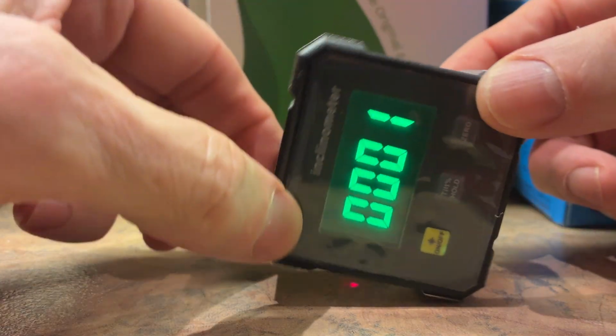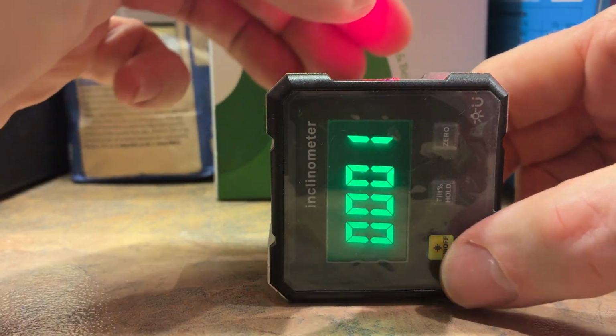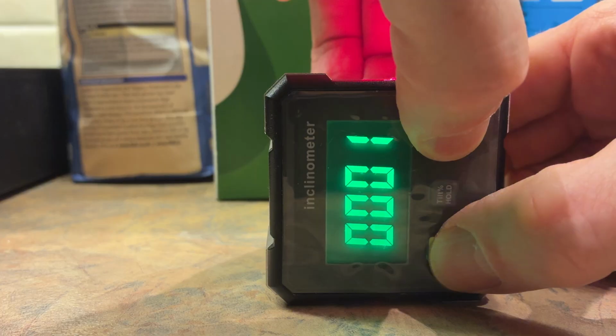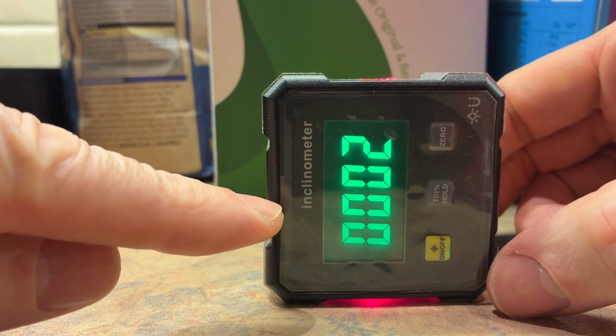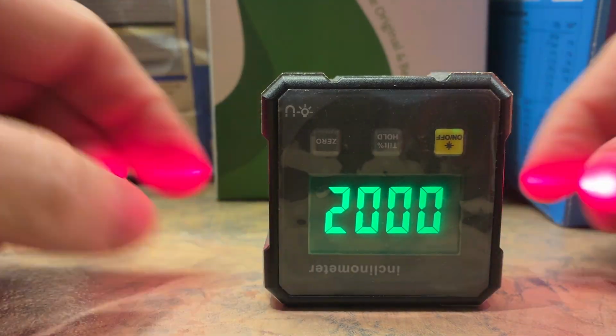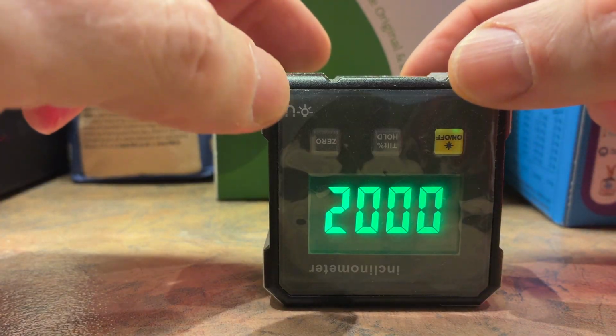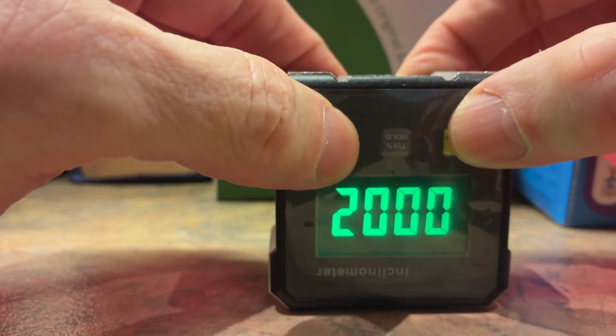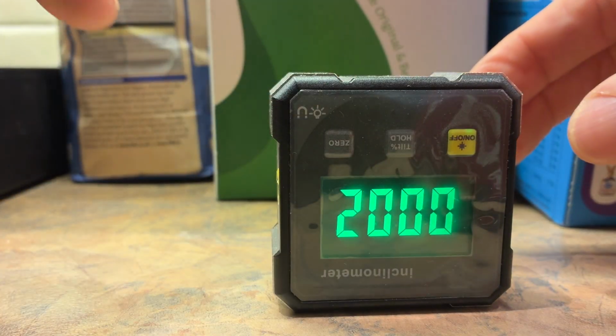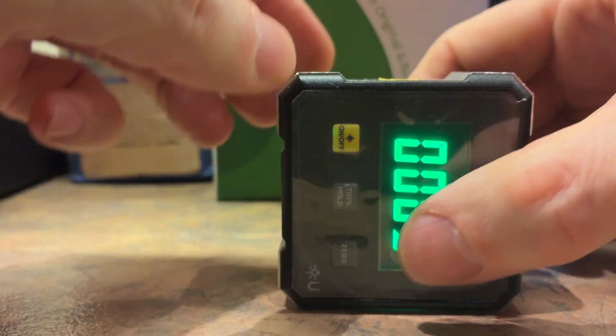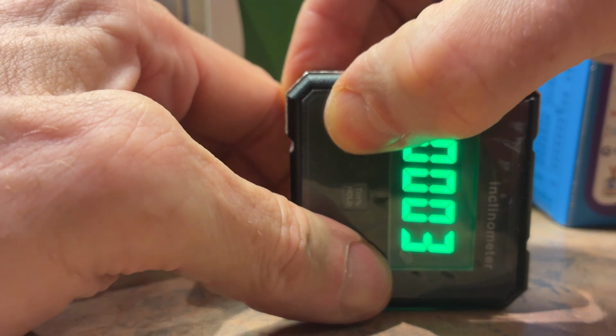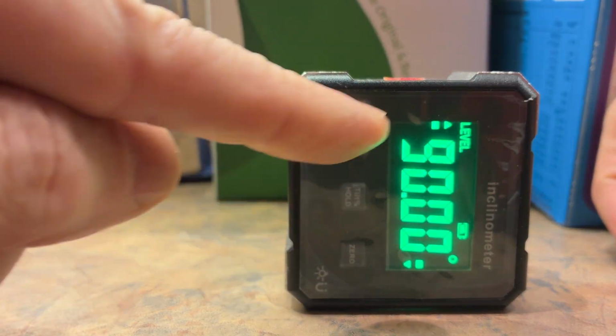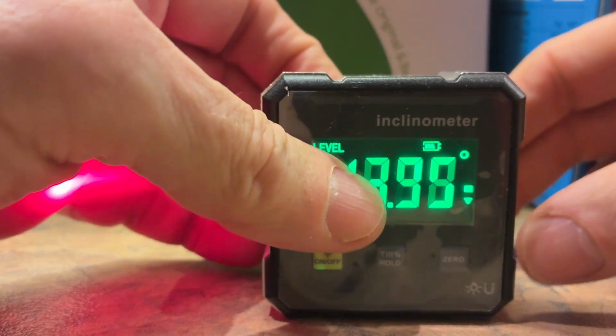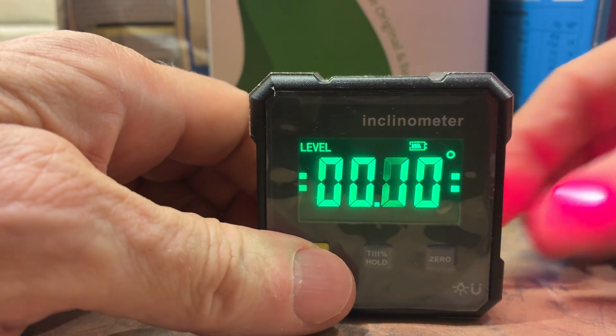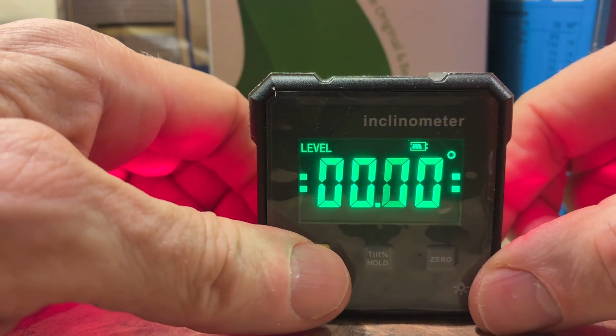So turn it 90 degrees, press and release the 0 and the on/off button again simultaneously, and release. Here we go. Flashing, gone to 2. It's turned both lasers on now. Remember, don't look into them. So on/off and 0. Flashing, gone into 3. Both of them again. Flashing, and this time it won't go to 4, it just says 90 degrees. And again, you can see that laser's on. So I'm just going to turn the laser off by a quick press and release. Let's turn that one on, quick press and release, turn them both on, quick press and release, and they're both off.